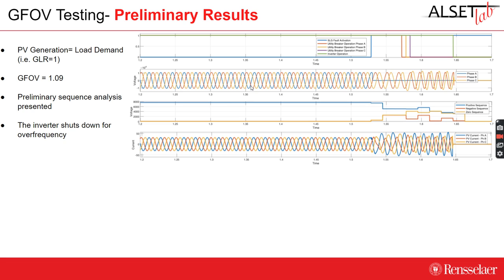Now we will show some preliminary results. We assumed that the generation of the PV was 500 kW and the load was 500 kW. When we applied the fault and after a few cycles the breaker operated, just after the breaker operation we can see that there was some overvoltage. The overvoltage was about 9 to 10 percent, which is significantly lower than the 73% of synchronous generators. To further explain this overvoltage, we did a preliminary sequence analysis. We can see that the positive sequence voltage reduces after the breaker opens, and the negative sequence and zero sequence pattern also changes. The inverter eventually shuts down for overfrequency. Our main concern is the time between the breaker operation and the inverter disconnection. For a generation-to-load ratio of 1, the overvoltage is about 9 percent.